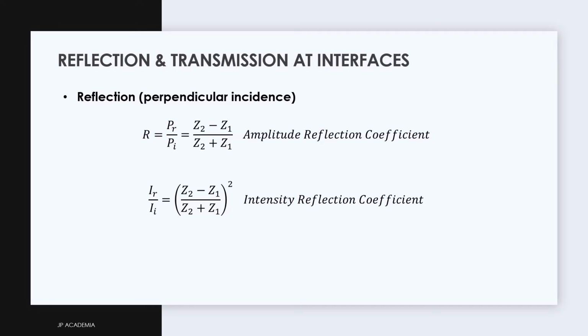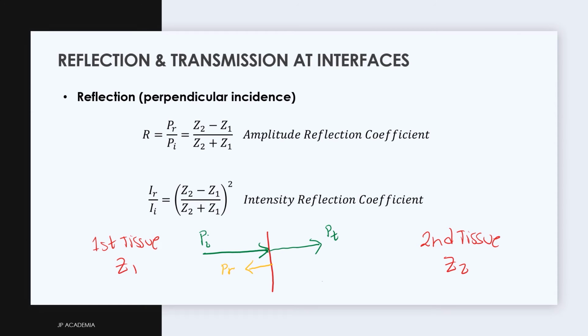When an ultrasound beam is incident to a certain interface formed by two different materials, as shown in the drawing below, for a smooth interface between the first and second tissue with different acoustic impedance values, a fraction of the energy will be reflected and the remaining energy will be transmitted. The amplitude of the reflected wave depends on the acoustic impedances of the materials. If the beam is in perpendicular incidence on a wide, smooth flat interface called the specular reflector, with dimensions greater than the ultrasound wavelength, the ratio of the reflected to the incident pressure amplitude is given by this formula.